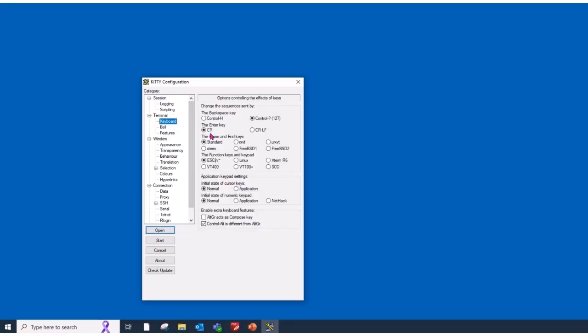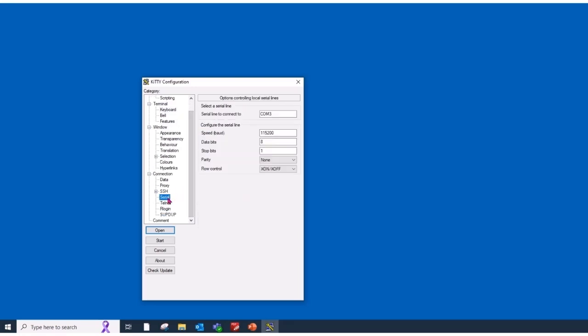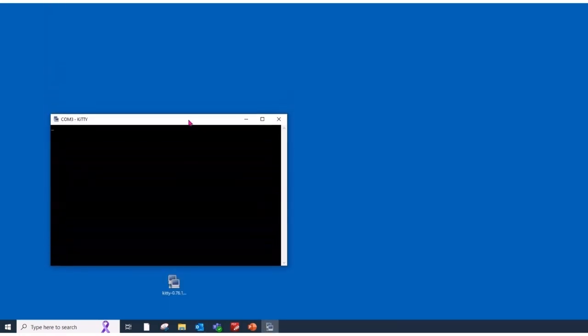Your Enter key, you want to make sure it's just carriage return, not carriage return line feed. It may affect a few things. And then the serial settings are over here if you needed to change them, but we don't need to. 8, 1, and X on, X off will work. And then you can open up and connect to the panel.